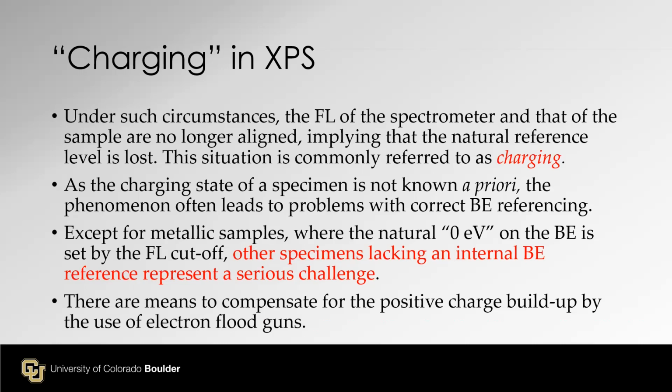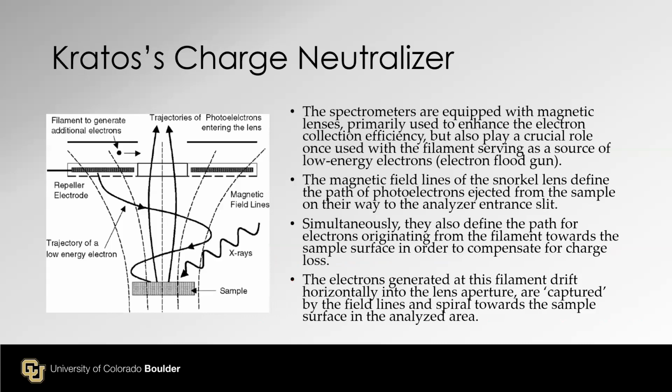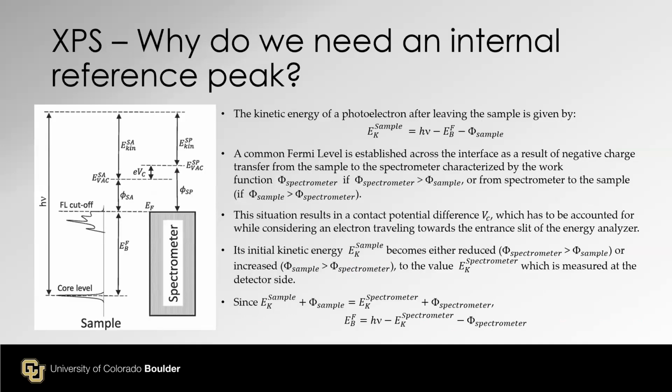Usually in XPS, X-rays come in and knock out core electrons, so the surface starts charging positively. So we can use electron flood guns of some kind to neutralize the surface. This is our charge neutralizer design.